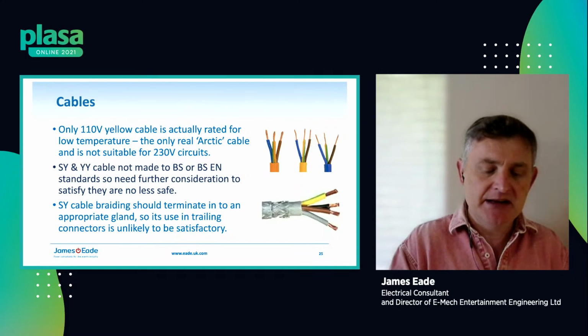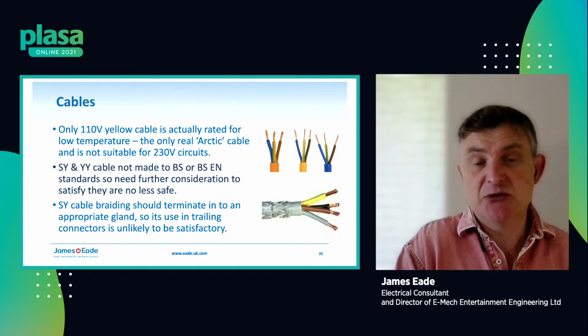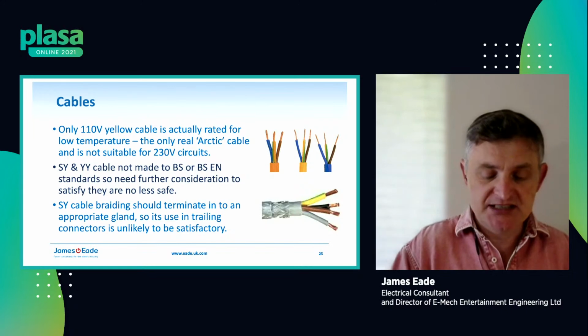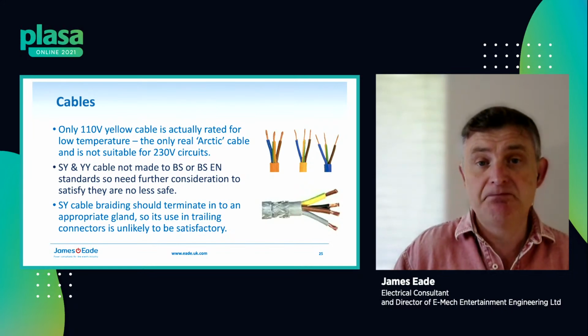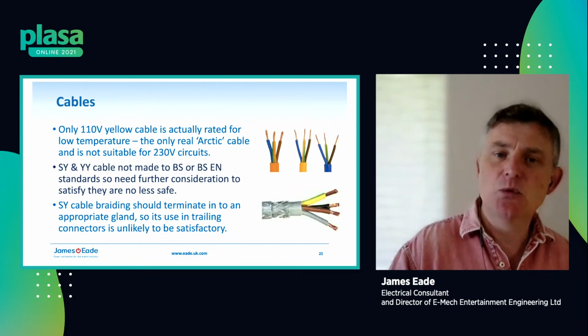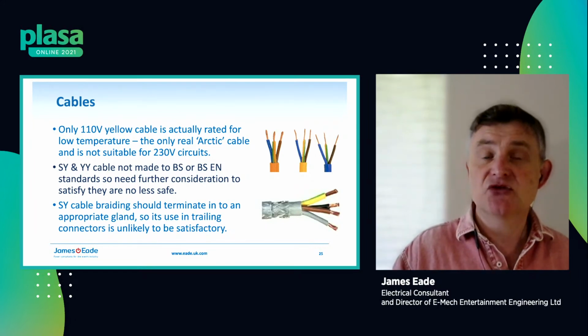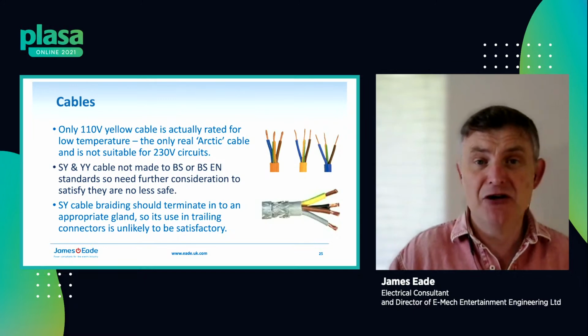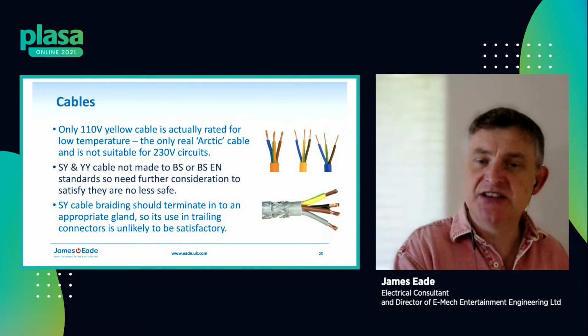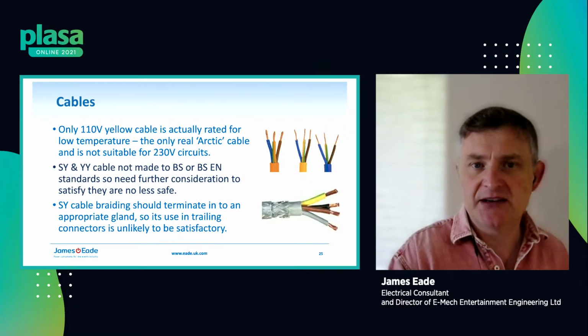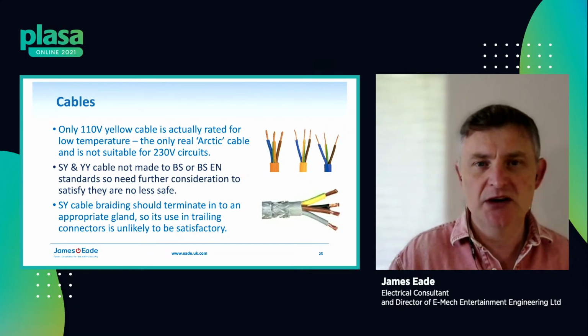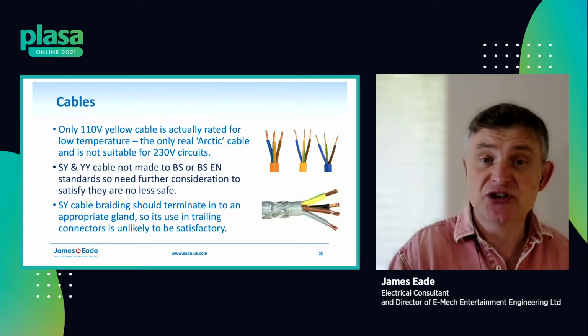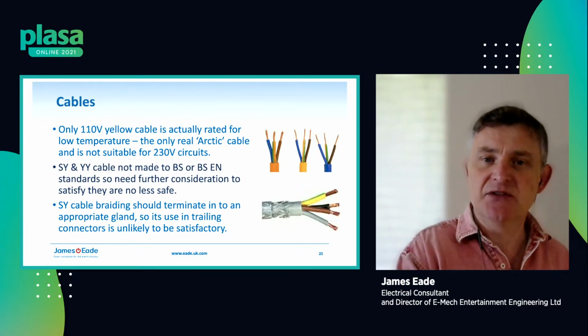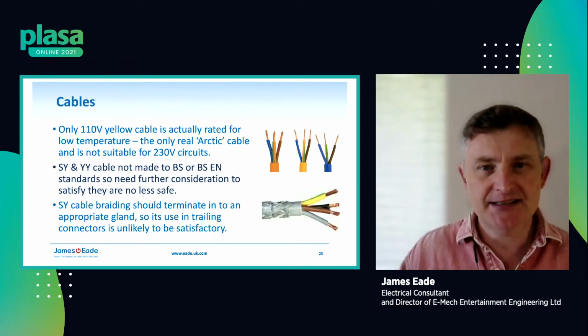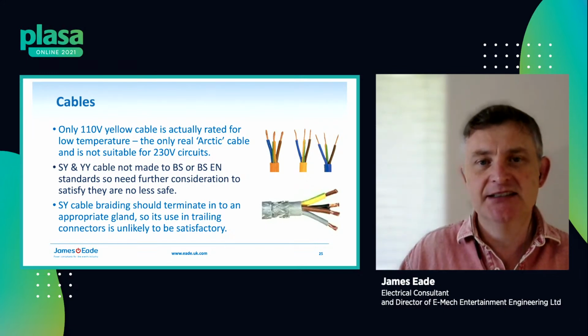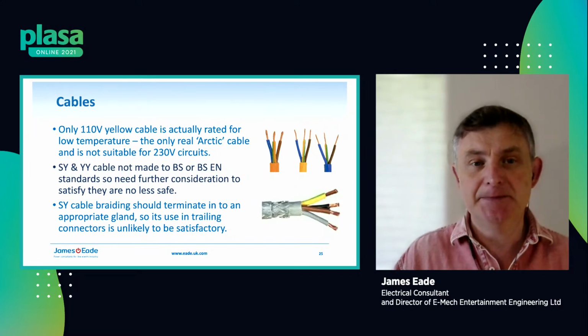So the real Arctic cable actually is made to a peculiar British standard, which is part of that reduced low voltage 110 volt construction site system. And the reason why yellow Arctic cable can be used on construction sites, which are very arduous environments, is because of the reduced low voltage system, whereby if you touch a live conductor, you'll only get a 55 volt shock to earth. So the risk of a severe electric shock is much, much reduced by the use of reduced low voltage. And so for that reason, plastic cables are cheaper and more readily available in that market.